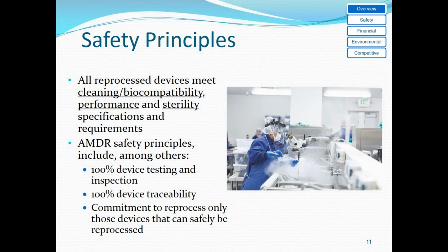all of our devices. So devices such as a compression sleeve or a tourniquet cuff, which are fairly simple, will be checked to make sure they can maintain pressure. Electrosurgical devices are hooked up to the generator to ensure that the electroconnectivity still works. Cardiac catheters are checked to make sure each of the electrodes on the distal end work. And so all devices are actually functionally tested. For those that cannot be tested, such as a saw blade or scissors, it will be visually inspected. So every device is individually tested or inspected, and that gives hospitals peace of mind.